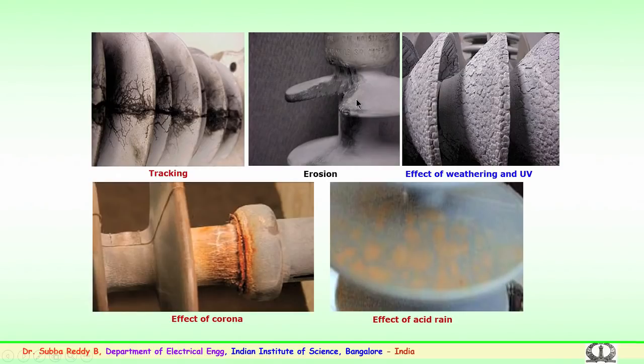This could happen because of several reasons as mentioned. It could be environmental issues, or continuous failures because of the material becoming harder, and the entire material has peeled. This surface erosion could bring down the entire creepage distance and the flashover happens. Then the effect of weathering conditions, which could be because of the sun, the ultraviolet radiation, or exposure to corona over a period of time. You can see the surface becoming stiff, becoming brittle, and the entire surface becoming hydrophilic, where it will be able to conduct and the failure happens.